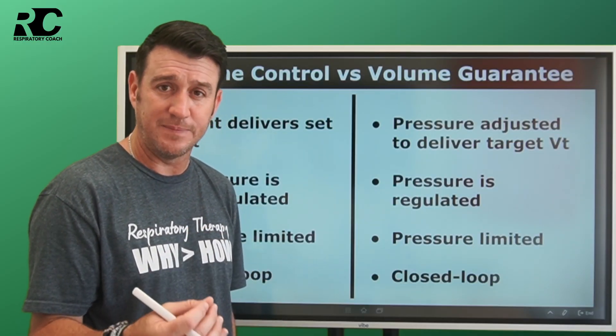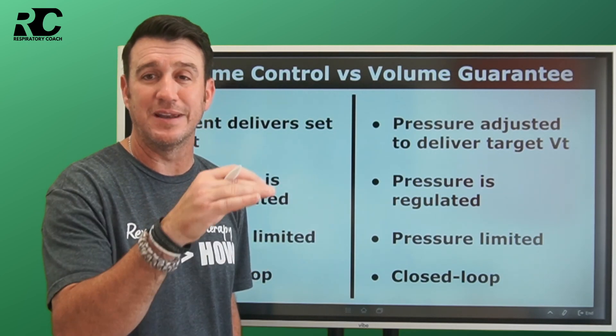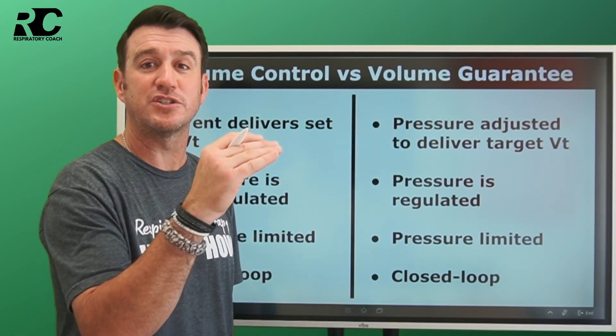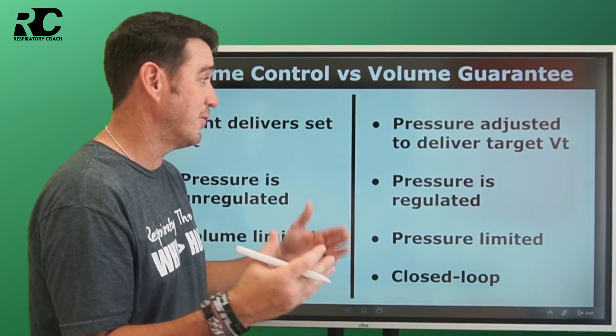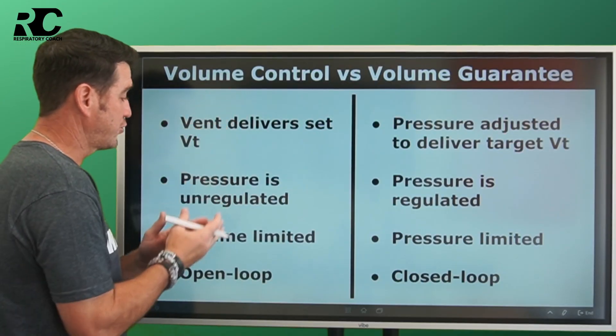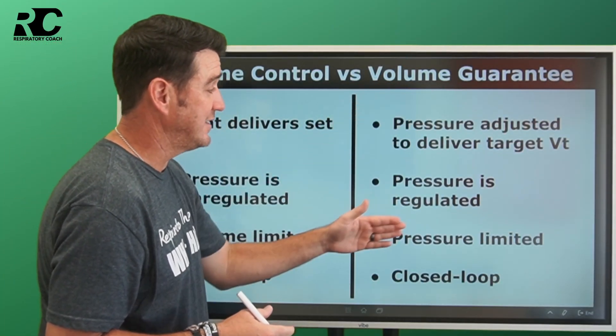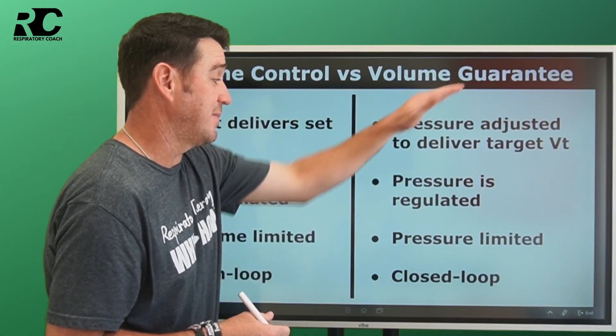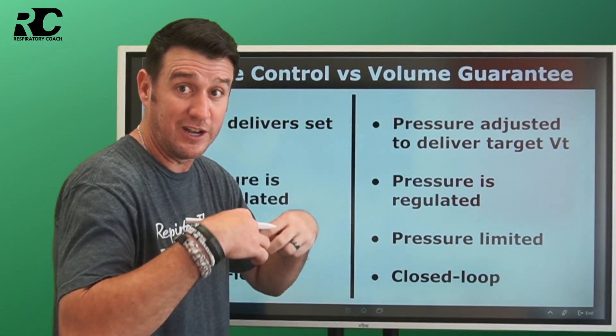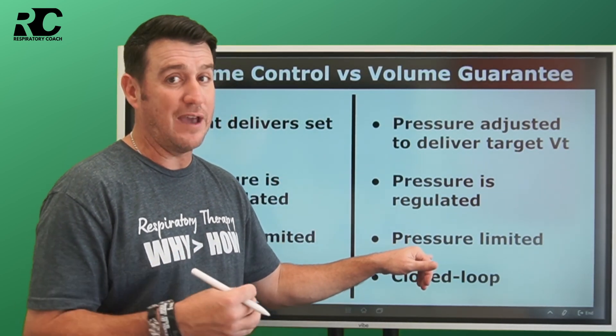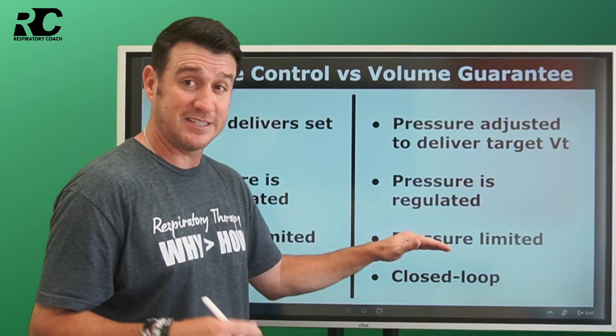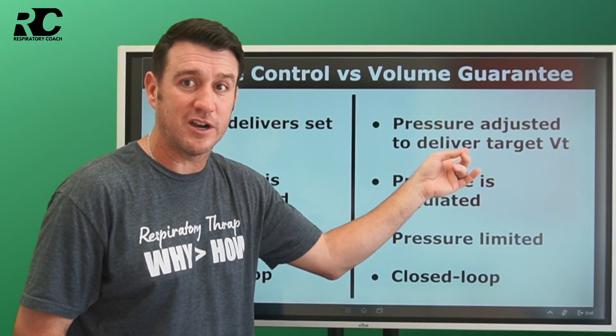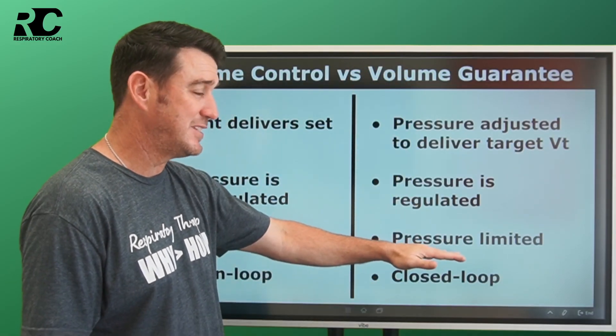Remember: in pressure control, if your patient's lungs become less compliant, volumes go down. So in volume guarantee, the ventilator turns up the pressure because volumes are dropping — it always comes back to compliance and resistance. Volume control is not pressure regulated; volume guarantee is pressure regulated. Volume control is volume limited and will not exceed the set volume. Volume guarantee is pressure limited — internally it will not exceed the set pressure limit. However, if compliance improves and pressure stays the same, you could get a tidal volume larger than target, so the vent will turn the pressure down.